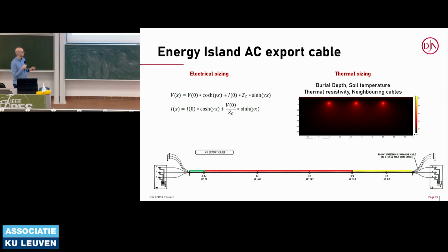Here, for example, at the area we call Scheur, there's a significant thermal issue because we need to bury the cable very deep, since vessels are passing by, so we have a higher cross section. Over here we have the J-tube, which is usually also a hotspot, because air gets trapped inside it. That trapped air can heat up but cannot cool down or be released, so there you also get a higher temperature.